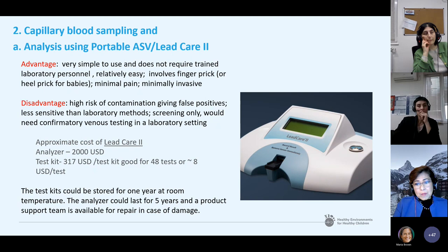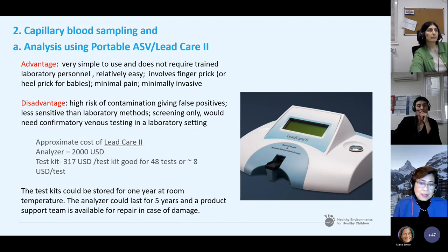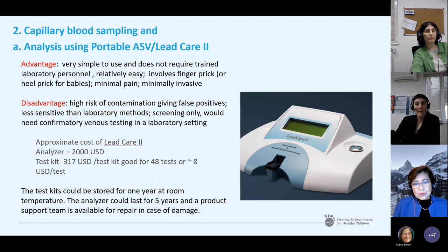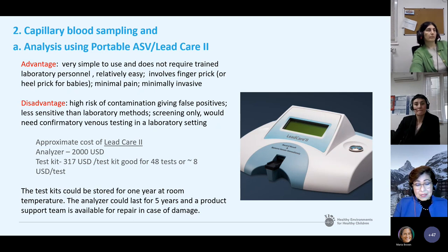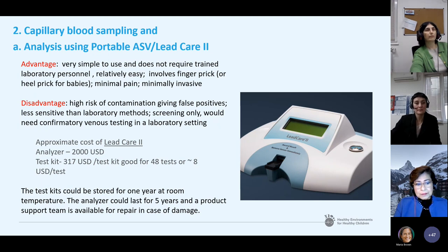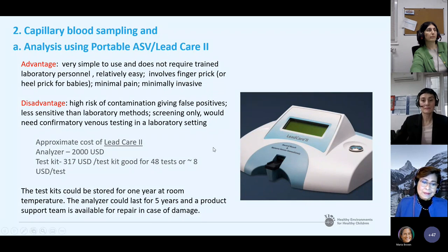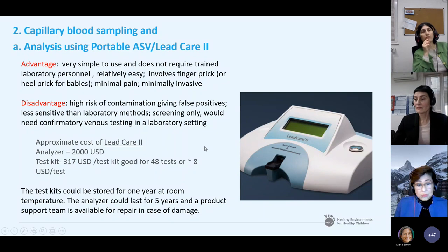Ideally, rather than using the LeadCare tool, it is better to send a sample — whether capillary or venous — directly to the laboratory, so you don't need a two-step process for high BLL cases above the 5 micrograms per dL reference point. The approximate cost as provided by the manufacturer is relatively cheap; however, questions remain about reliability, accuracy, and precision. The analyzer can last five years and test kits can be stored for one year at room temperature.